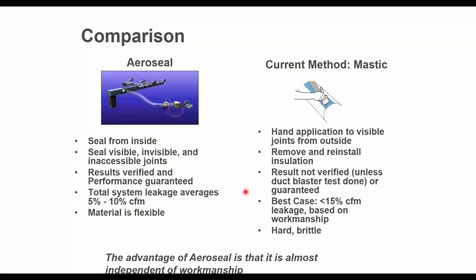Yes, it will seal down to a lower leakage rate than doing it by hand. Even if you're really good at doing it by hand, people always miss stuff, right? That human element, you just don't get to everything. Or you get to three sides of the duct and you can't get to the fourth side because the fourth side is literally pushed up against a ceiling joist or something like that, and you physically can't get there. It's impossible. So you do get a lower leakage rate because you can get to everything.